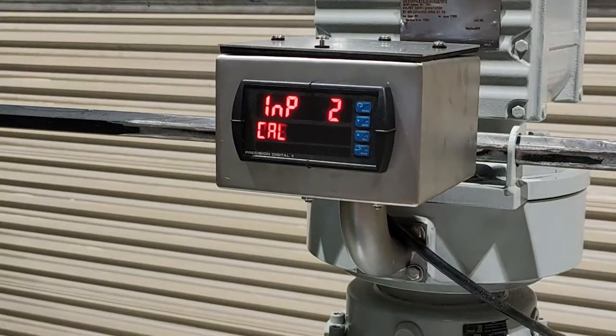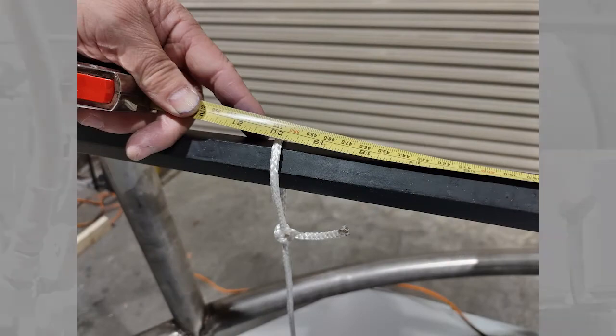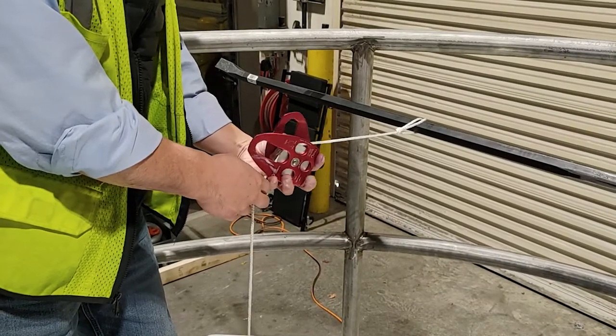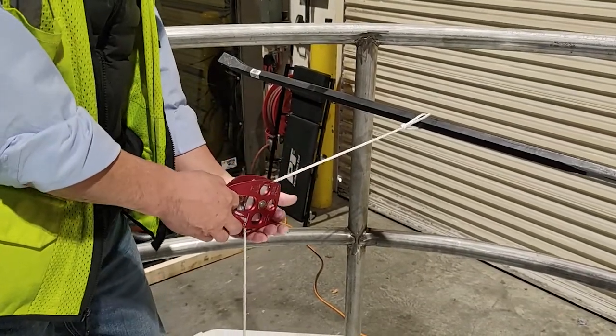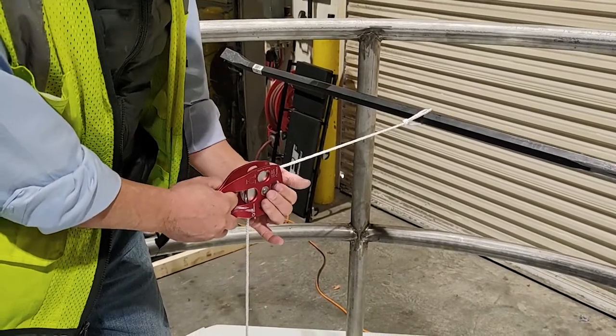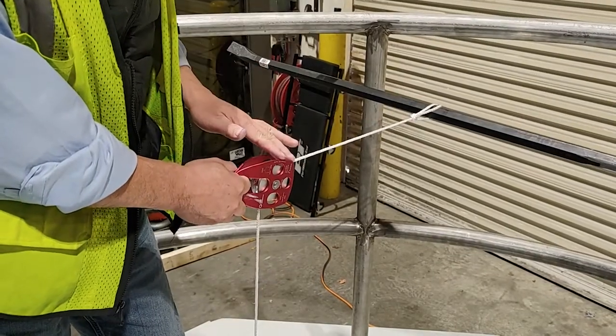The display on the screen should now read INP2. This means that the calibration program is looking for the active state set point signal. Ensure that the setup of your pipe, rope, and weight has not shifted. Place the pulley on the rope between the pipe and the weight. Hold the pulley so that it is in line horizontally and perpendicular with the pipe.